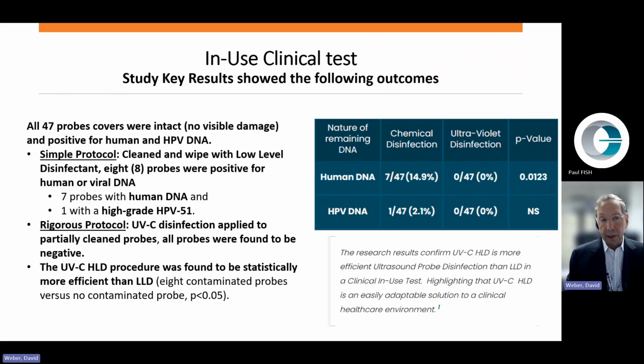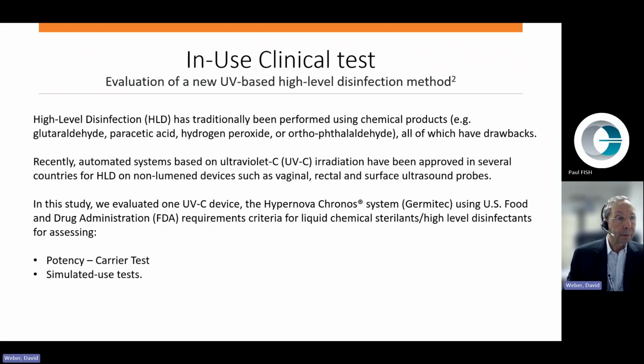In the upper right, you can see a chart that demonstrates these numbers. Again, human DNA, chemical disinfection, positive 7 out of 47, approximately 15%. Ultraviolet disinfection is 0 over 47, 0%. HPV DNA found in 1 over 47, 2.1%, with chemical disinfection, found in 0 over 47 with ultraviolet disinfection, 0%. This research confirmed that UVC high-level disinfection is more efficient for ultrasound probe disinfection than low-level disinfection in a clinical use test, highlighting that UVC high-level disinfection is an easily adaptable solution to a clinical healthcare environment.